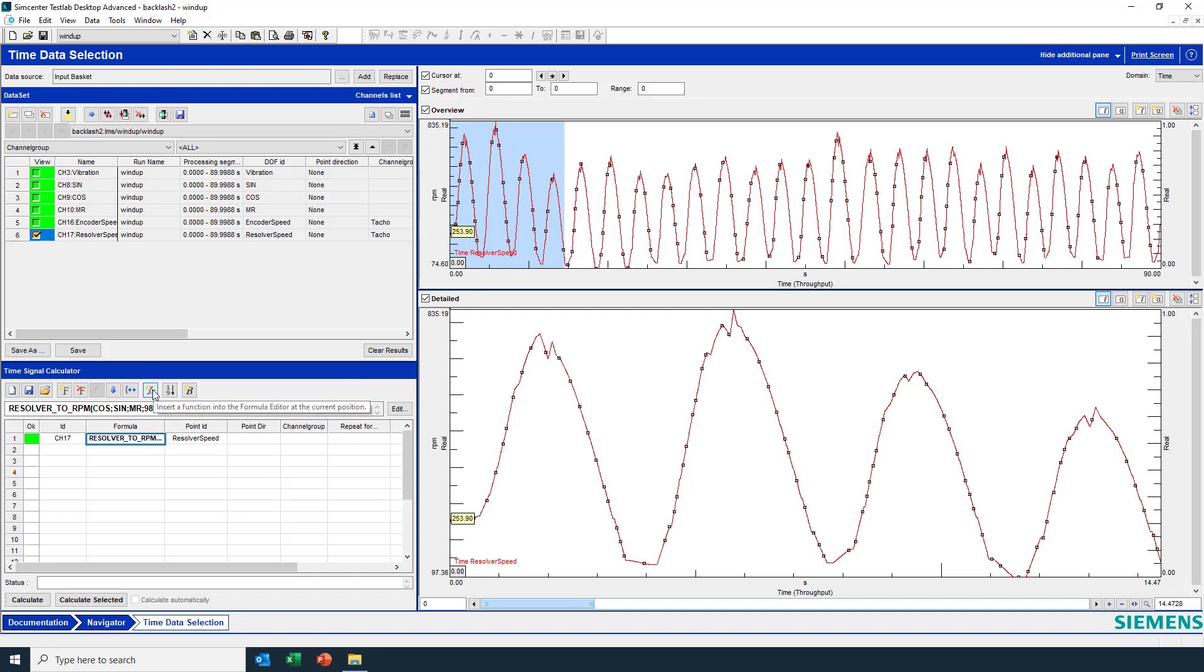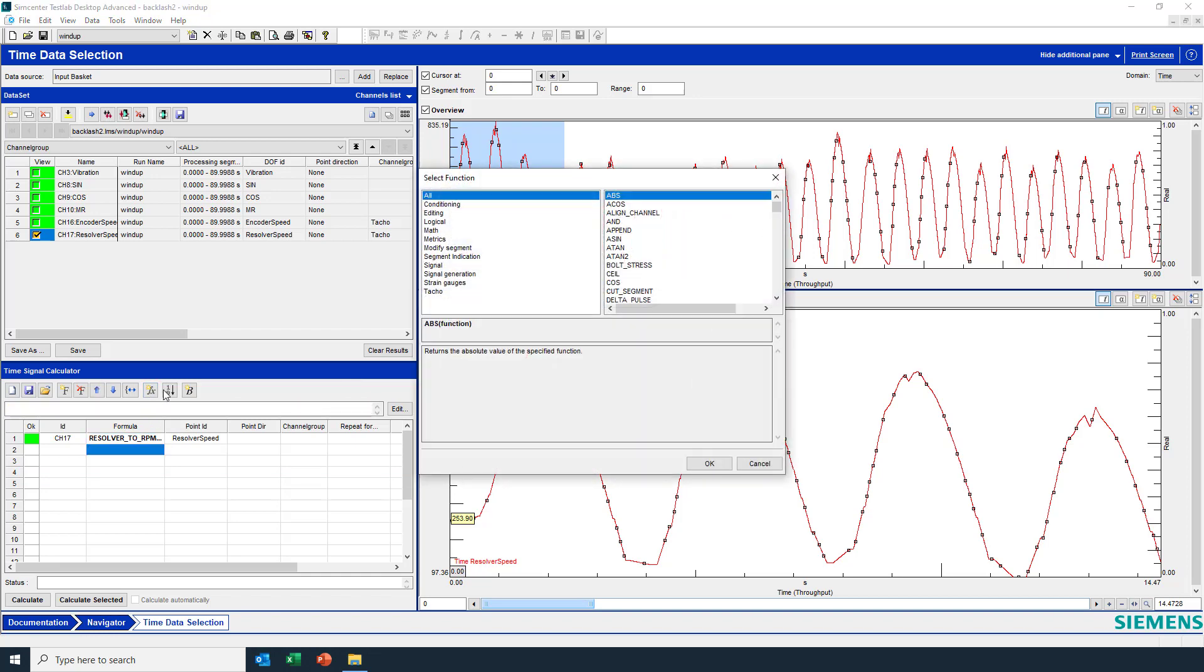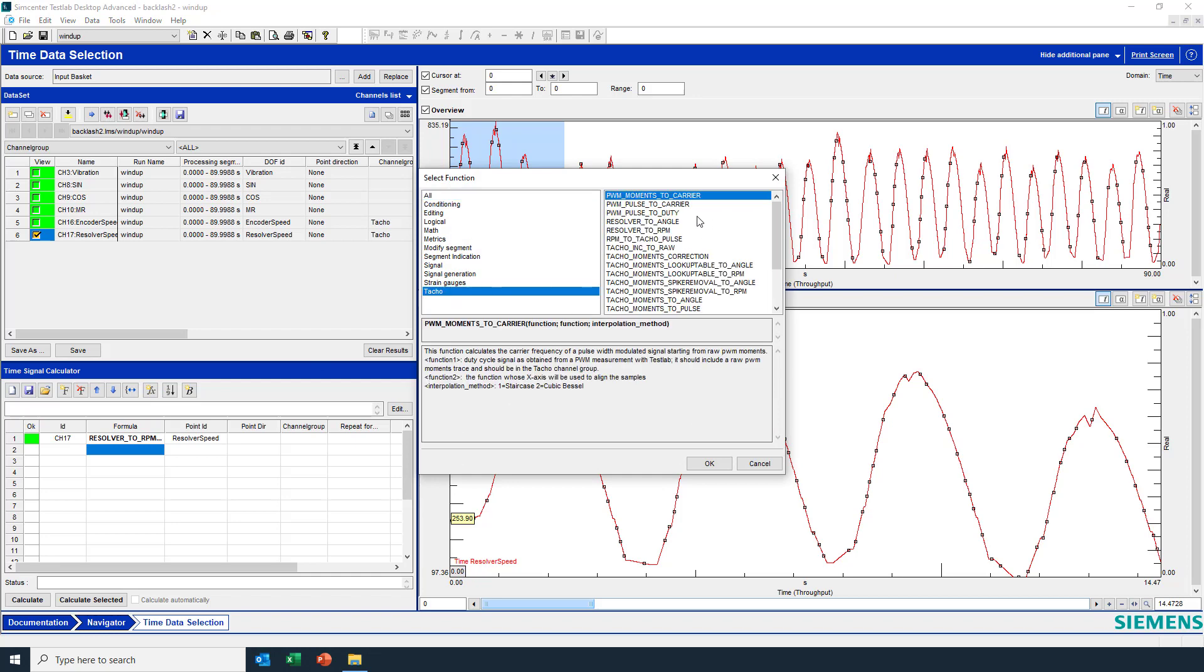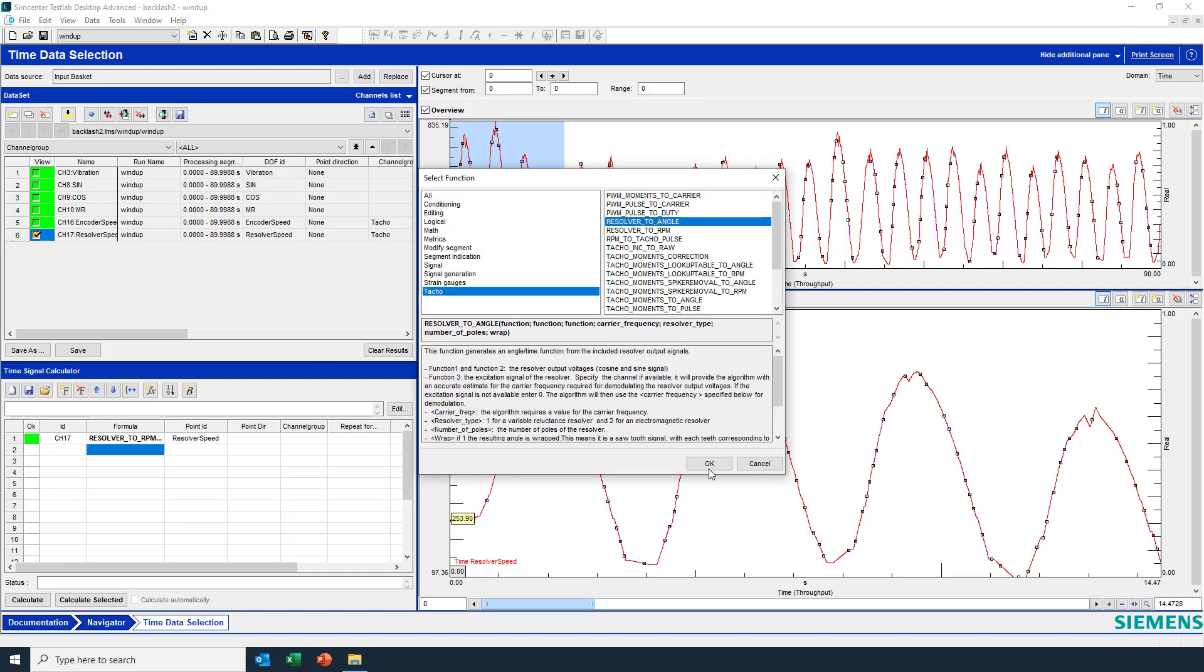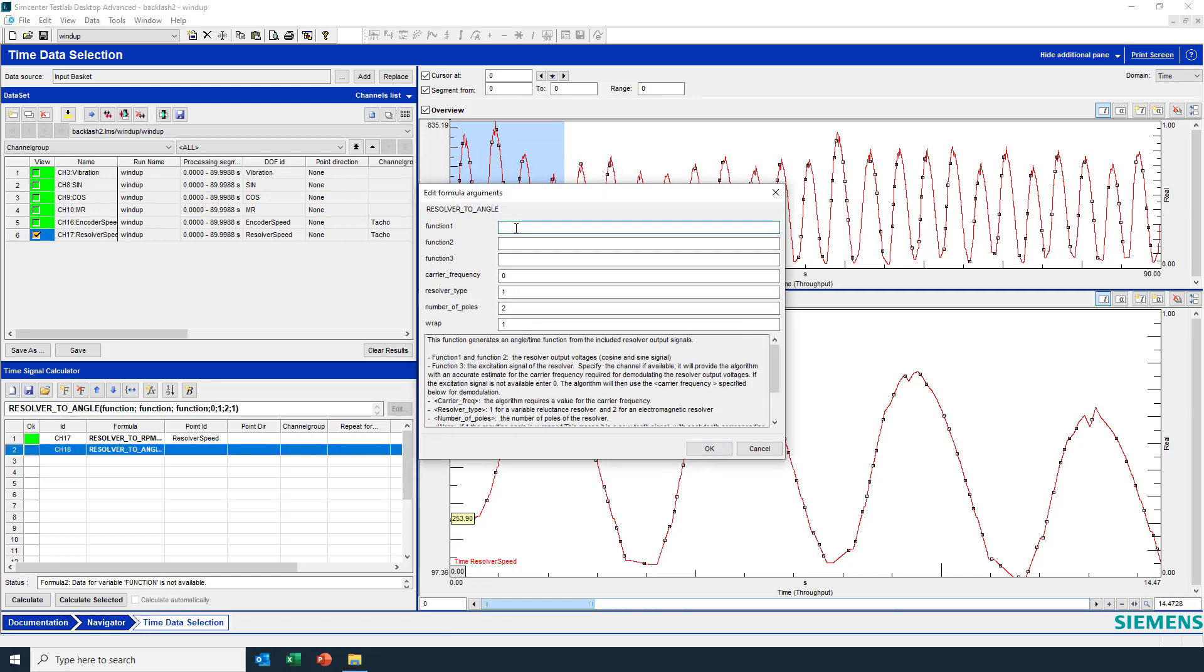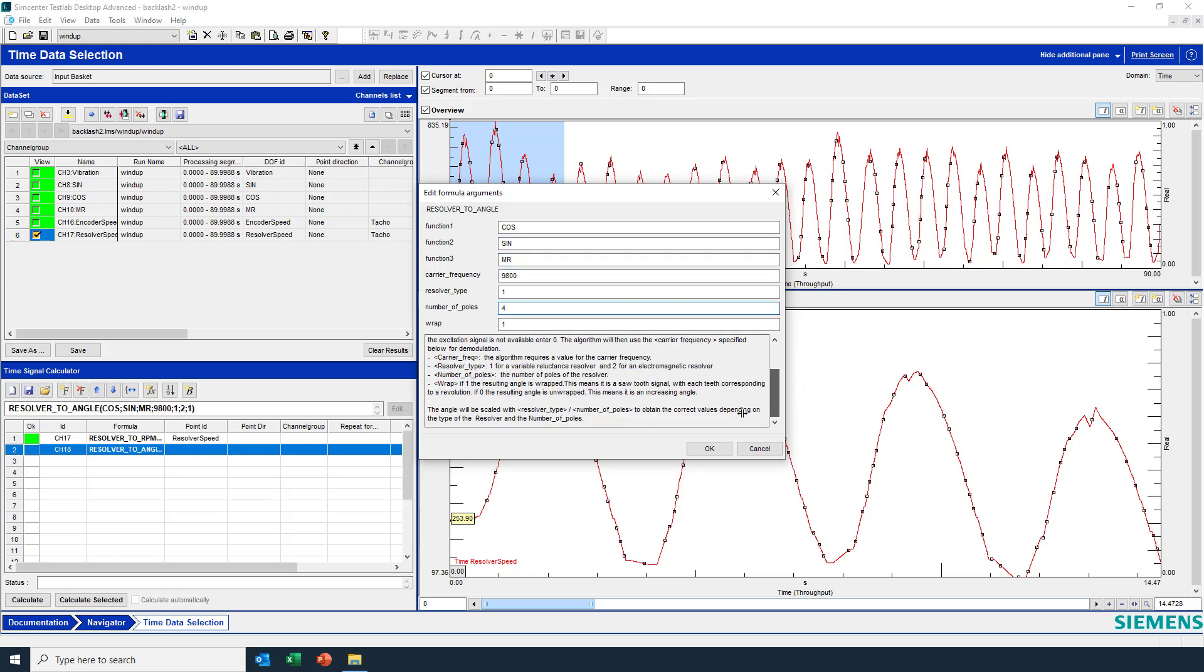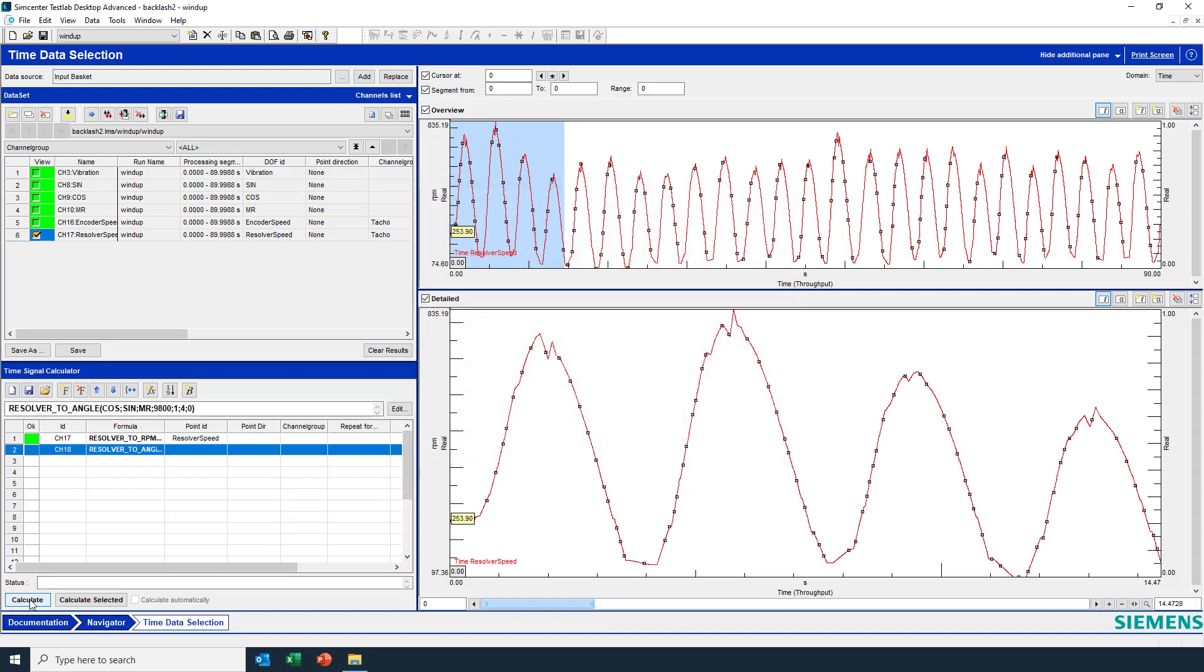I'm interested in the angle. So what I'll do is I'll also calculate the angle for the resolver using resolver to angle here. I'll enter the same parameters as before now that I know they're correct, but now I'll be getting the angular position. And I'm going to say I want the angle to be unwrapped so that it continues increasing, doesn't bounce between 0 and 360, because I want to calculate the angular position across the entire time.